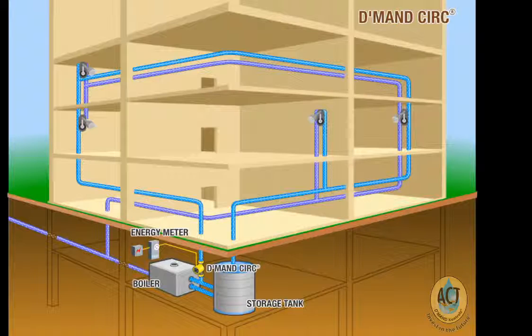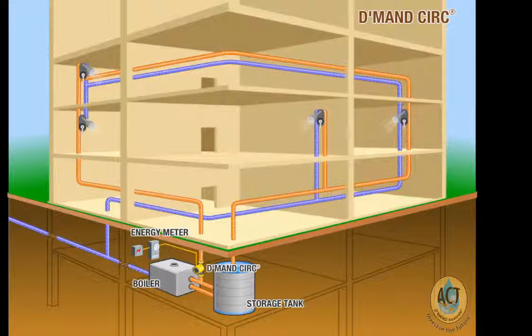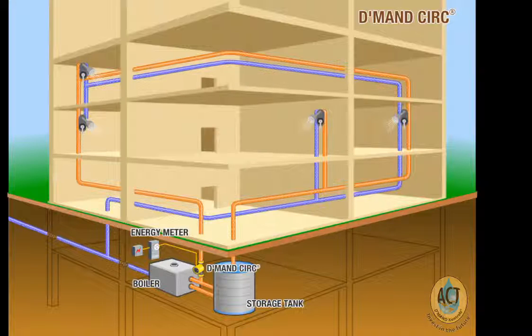The Demand CIRC uses sensors that monitor real-time hot water usage in the building as well as loop temperature. When the Demand CIRC detects a combination of hot water demand within the building and cooler ambient temperature water in the loop, it kicks on to deliver hot water throughout the building within seconds.